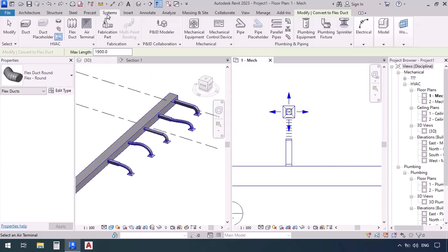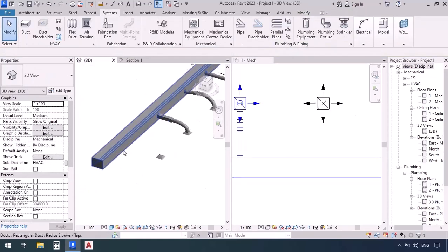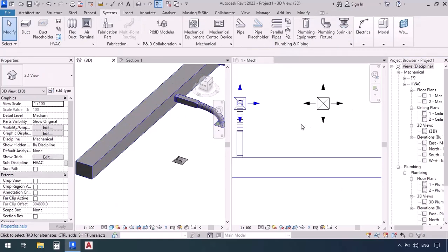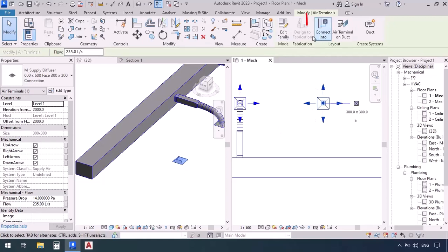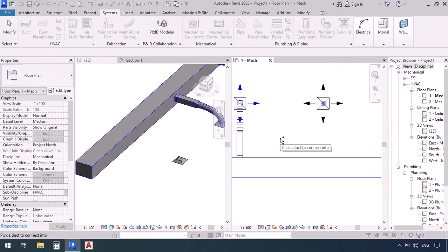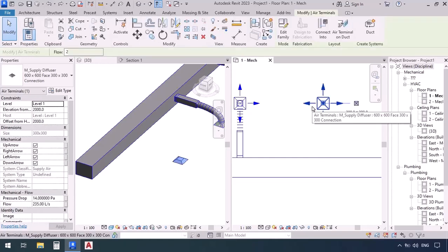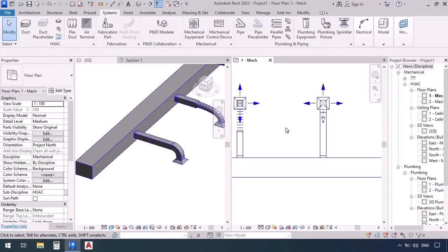Let's try another method. Go to the systems tab, air terminal command, and place another terminal. First click on the terminal to select it — up in the ribbon we see an option called 'Connect Into.' Click it, and then click the duct we want to connect into. Without having to select the duct command, we were able to connect this terminal to the duct. Revit takes the settings from the fitting types and properties that the duct has to determine which fitting types to use.